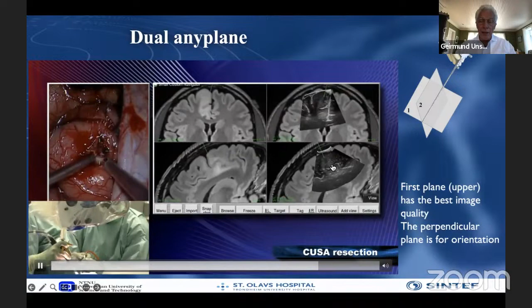I think the absolutely best display technique is to use the tip view. This upper plane is parallel to the probe, more or less, as shown in this blue square. And the lower plane is shown in the red square, and it goes through the tip of the instrument. And here you get both best qualities of the ultrasound probe, the axial and the lateral. And you get a very good image quality, and it's also very intuitive because you get an image that is more or less identical to what you see in the microscope.